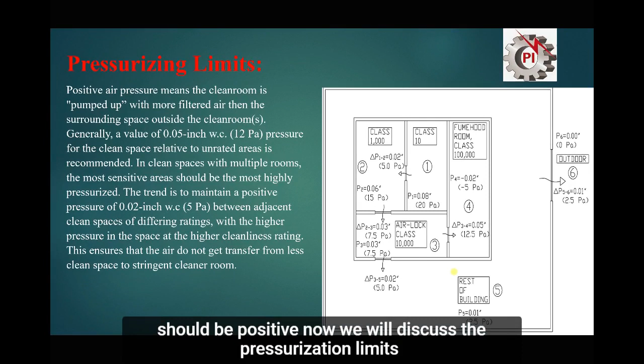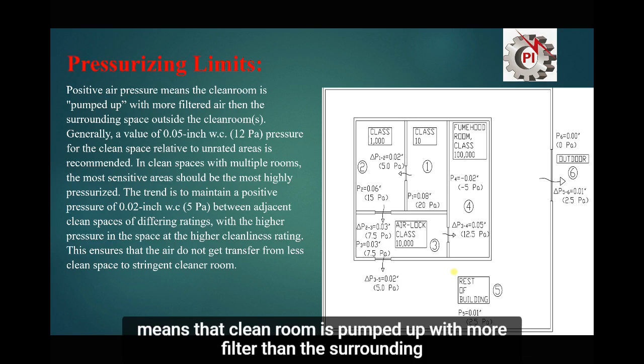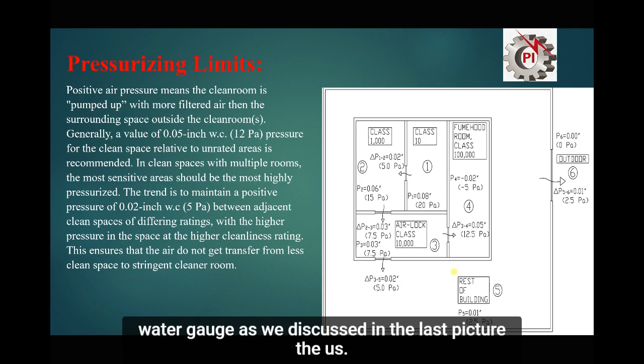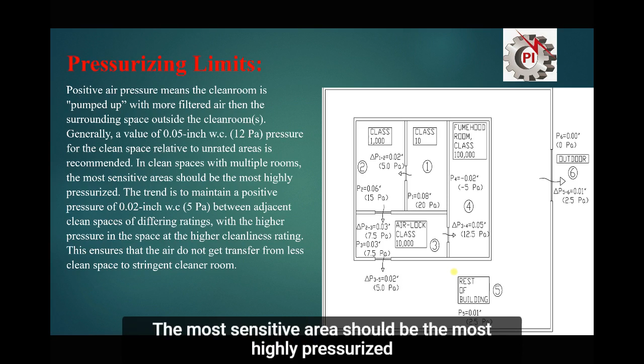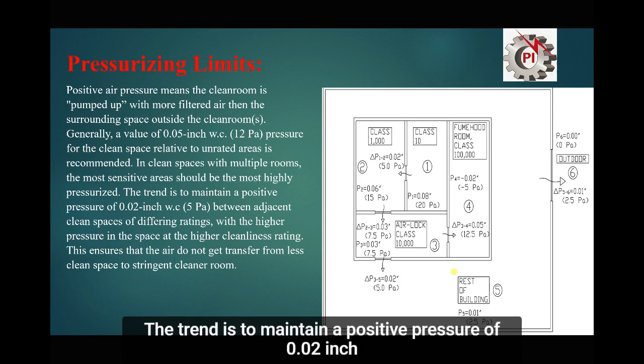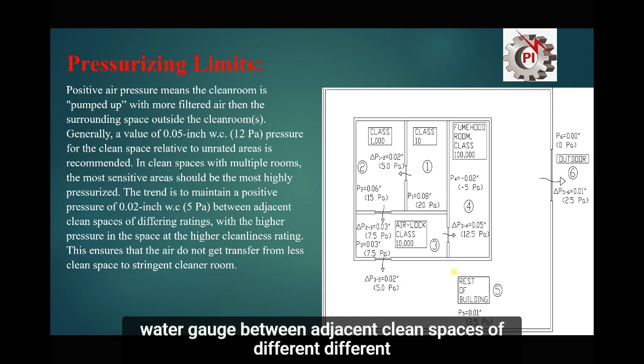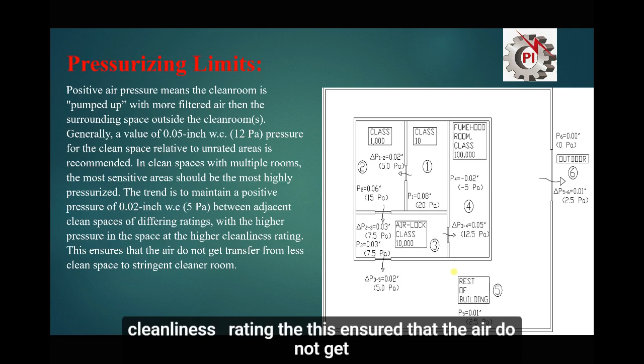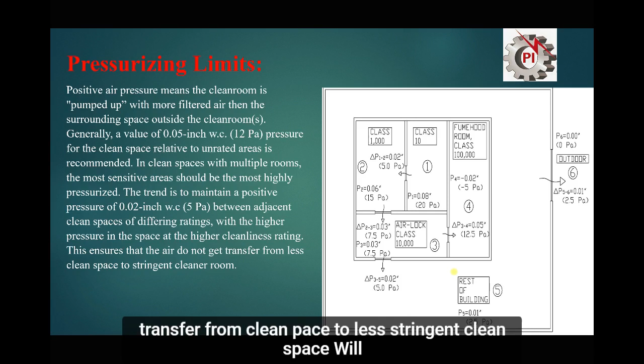Now we will discuss the pressurization limits. Positive air pressure means the clean room is pumped up with more filtered air than the surrounding space outside the clean room. Generally, a value of 0.05 inch water gauge, as we discussed in the last picture, the US guidelines, pressure for the clean space relative to unrated area is recommended. In clean spaces with multiple rooms, the most sensitive area should be the most highly pressurized. The trend is to maintain a positive pressure of 0.02 inch water gauge between adjacent clean spaces of differing ratings, with the higher pressure in the space at the higher cleanness rating. This ensures that the air does not get transferred from less clean space to the more stringent cleaner room.